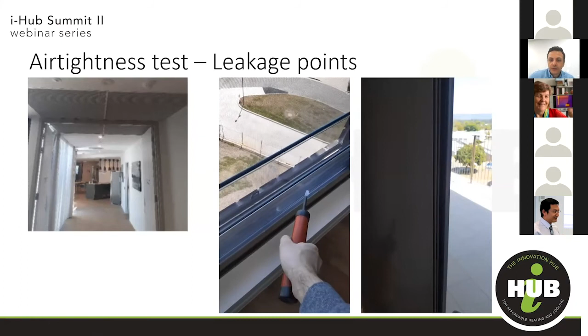The other location was between the two doors of the sliding doors, so that's the joint between the sliding door. Other areas of leakage were the perforated ceiling. We're not sure whether that's because of the ceiling space itself or because there are actually some leakages on the roof, so it might be a good idea to test some sealing solutions to make the building more airtight, perhaps finding a way to better seal the window frames, and then run the test again.